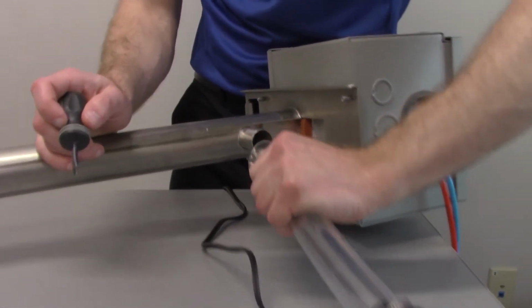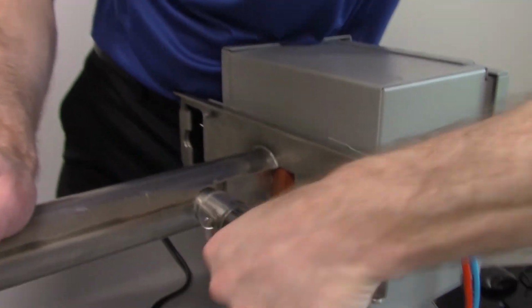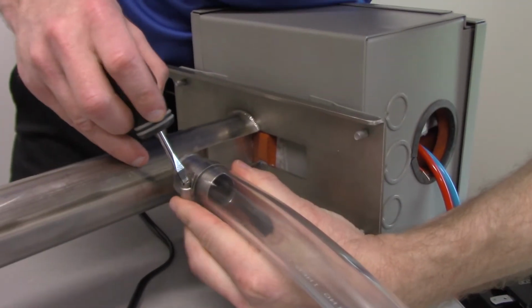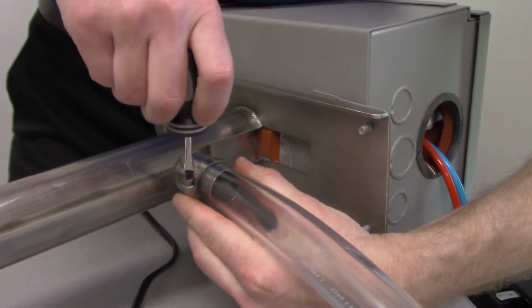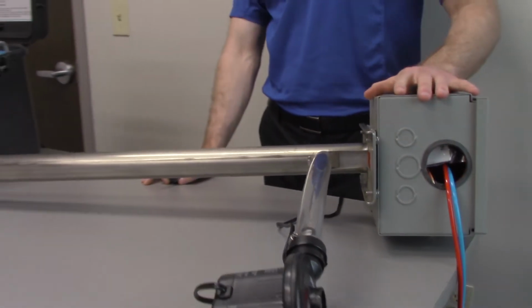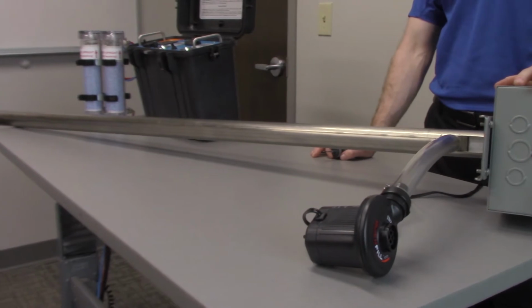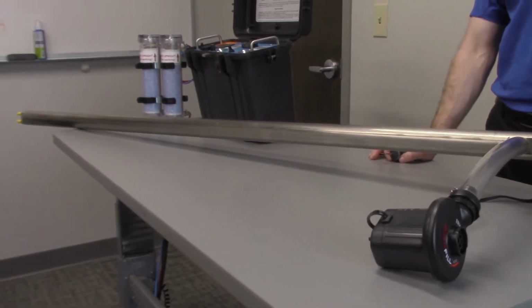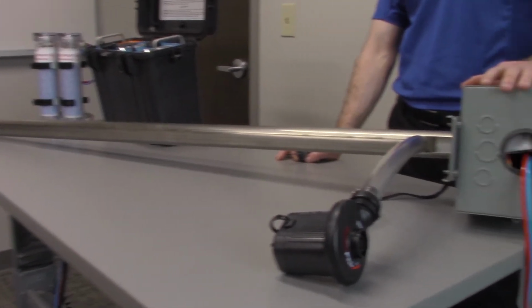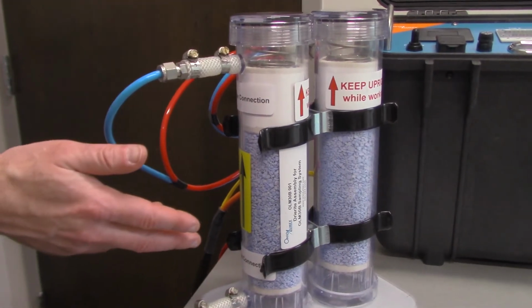The cooling air inlet is used to attach either compressed plant air or air from a portable blower to the probe in order to bring probe temperature down in particularly hot sampling environments. The cooling air is pushed down through a cooling tube into the interior and then exhausted at the back of the probe. The desiccant canisters contain 2 materials.